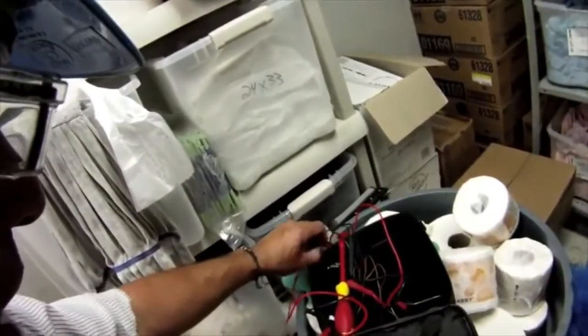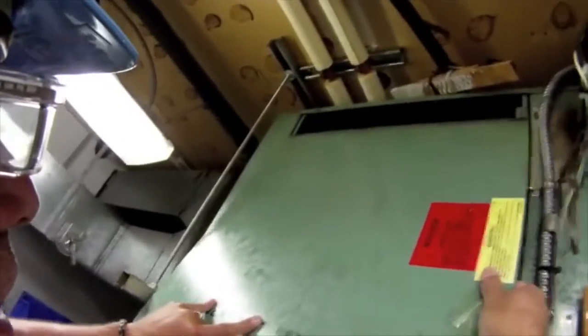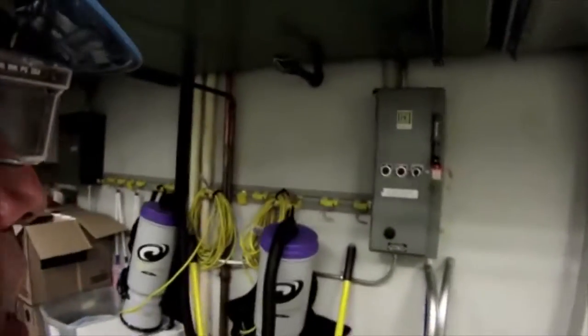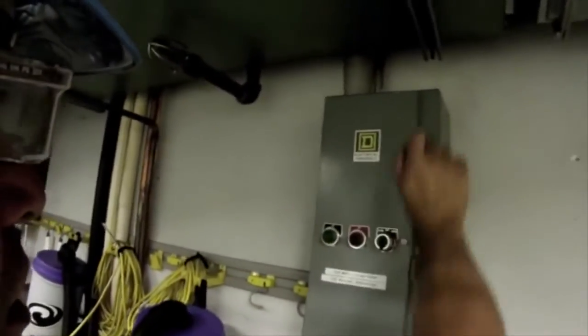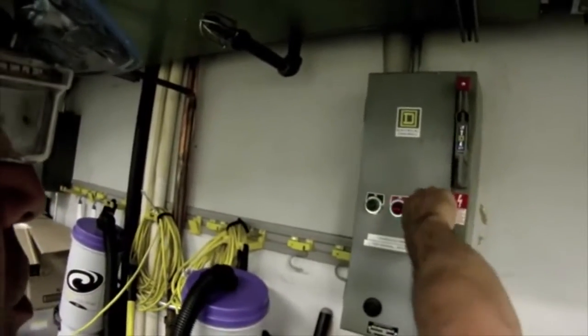And then I'm going to put my cover back on. Once my cover's back in place, I can energize the circuit. I can get an amp draw on this motor. And then we'll go over to the starter contactor, energize it, energize the controller, wait for the fan to come on. Once the fan comes on, I'll be able to get an amp reading without using any PPE other than my safety glasses.